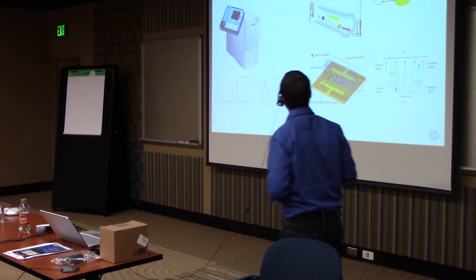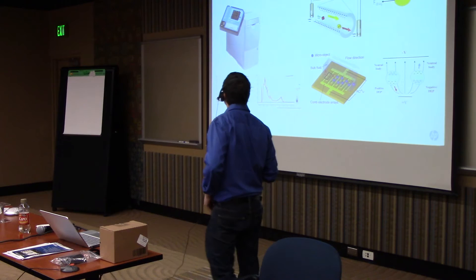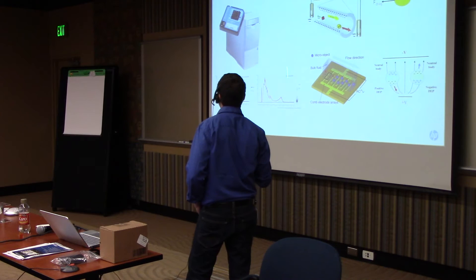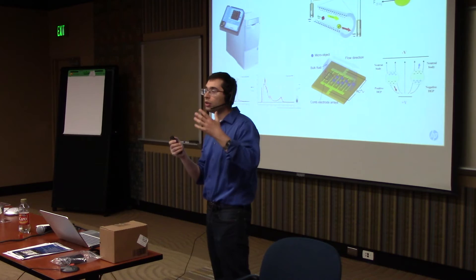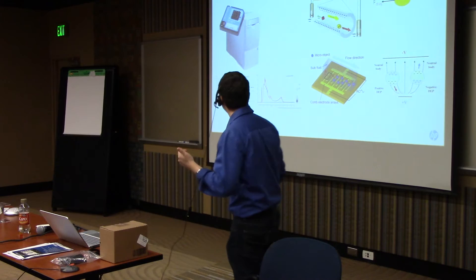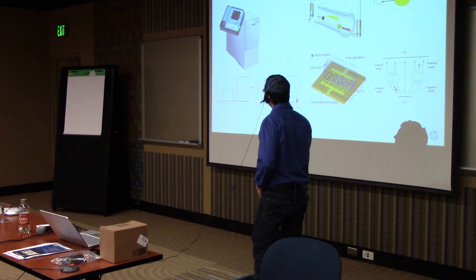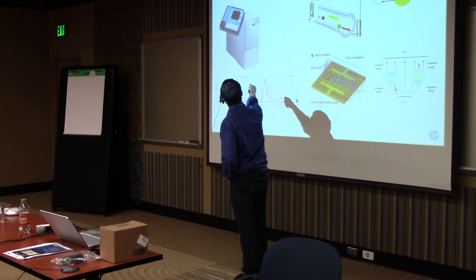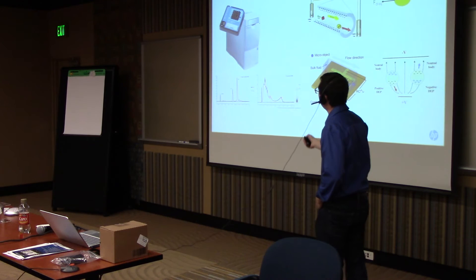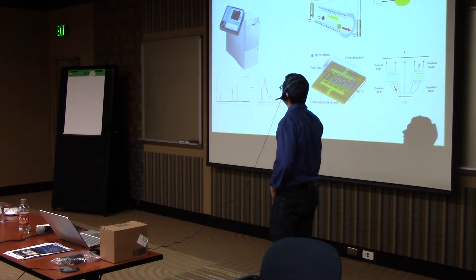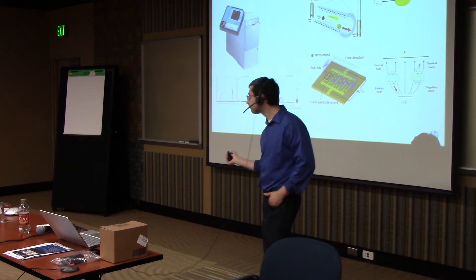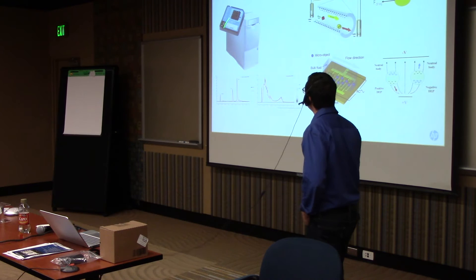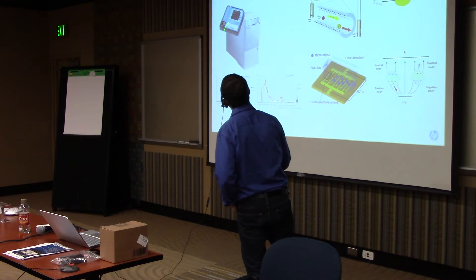But you can do a lot more things when you cut off that resistor and just use those electrodes for something other than heat. So here, I'll just show you very briefly and then I'll start the next presentation. What you can do with electrokinetic microfluidics. So the simplest thing is you can do electrophoresis where you can separate your analytes based on the ratio of the charge to their drag in a particular medium where you put in. And turns out this device with this little chip, this takes little chips, is called a bioanalyzer instrument. And so it's very hard to see, especially on the screen. It actually says HP Bioanalyzer. So this is an instrument that was built prior to the HP Agilent split. And it's now sold by Agilent. It's a very, very successful instrument to do electrophoresis, in particular gel electrophoresis. And I'll explain how all this works just shortly.